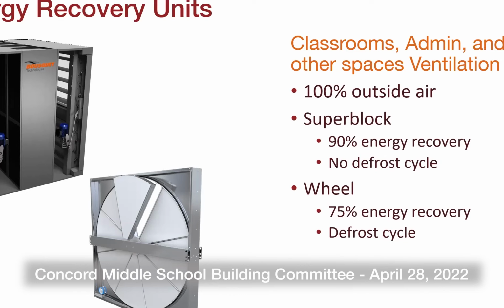Great, yeah, so defrost cycle - the wheels aren't just getting heat from temperature, they're also getting it from humidity. When they're doing that with cold entering air temperatures, there can be frost buildup on the wheel, which makes it so it doesn't work quite as well. So wheel manufacturers program in a defrost cycle, which basically prevents energy transfer - incoming air just bypasses around the wheel while it warms up and gets rid of any frost buildup. This is essential for the wheel to function well, but it means that while this is happening, you're bypassing the wheel and not getting 75% energy recovery.